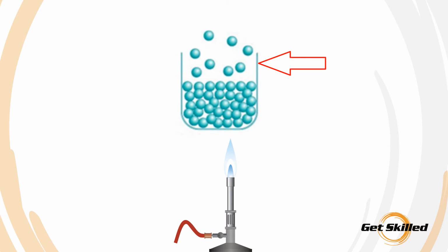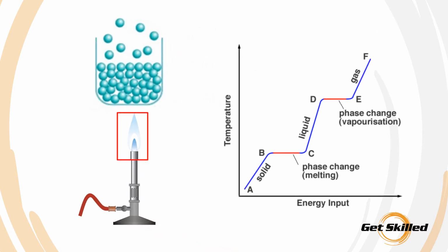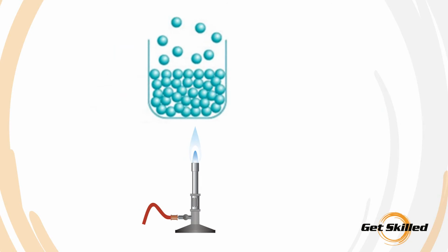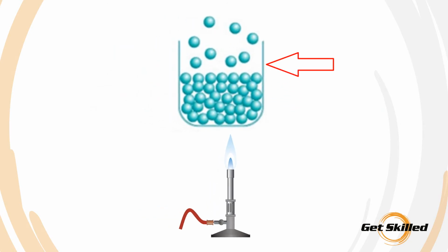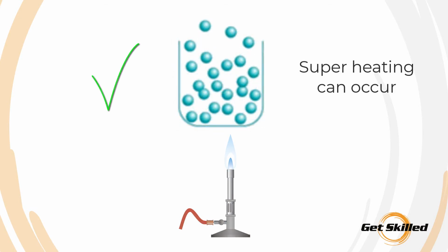As long as the vapor remains in contact with the liquid, it will be saturated. This is because any heat added to a liquid-vapor mixture will result in latent heat vaporizing more liquid and no superheating will occur. When the refrigerant is both a liquid and a vapor, it cannot be a superheated vapor. The refrigerant will have to be a complete vapor for superheating to occur.